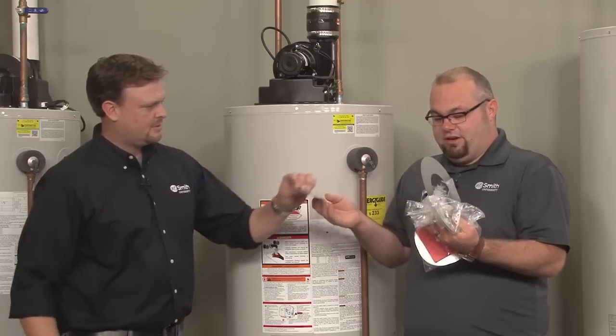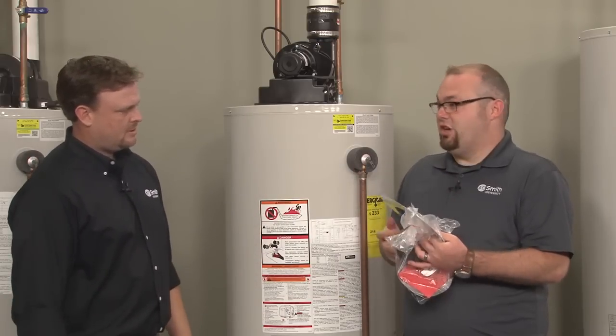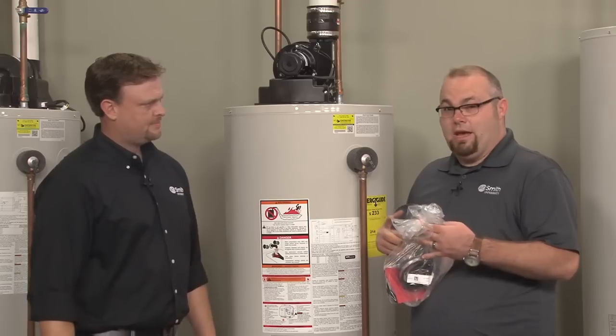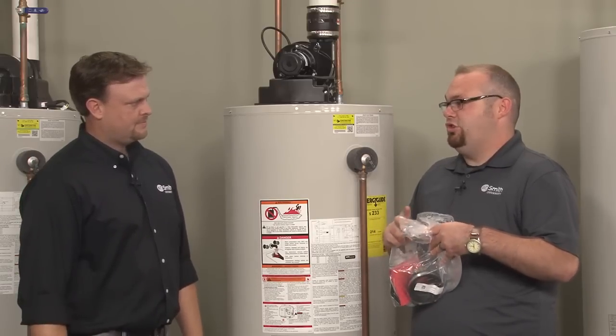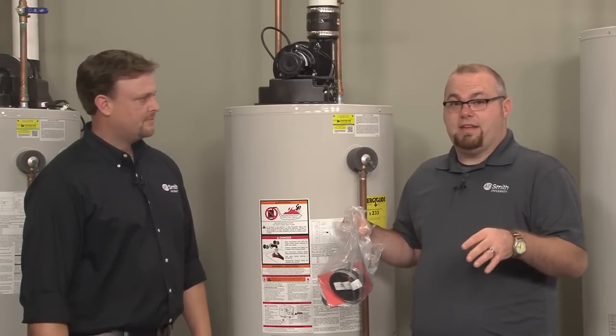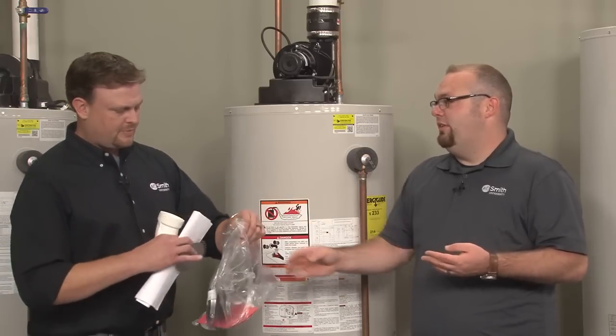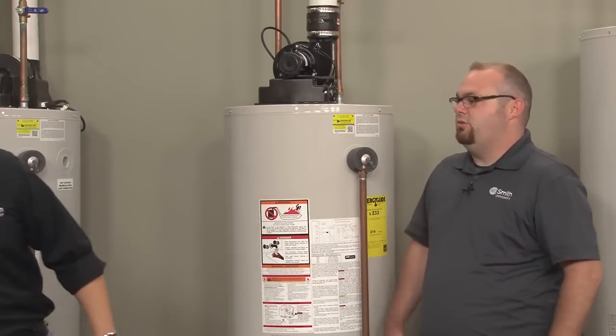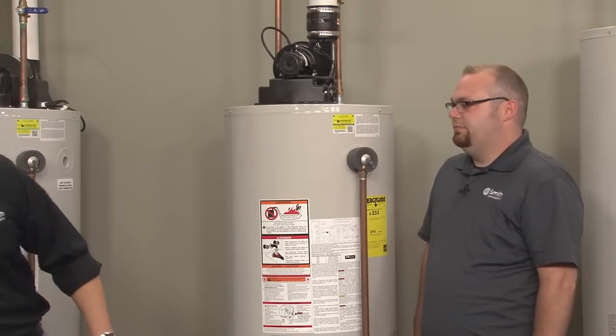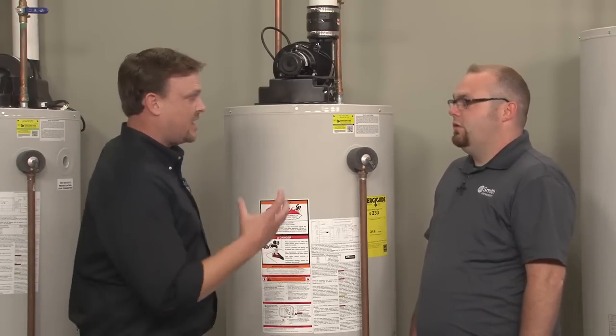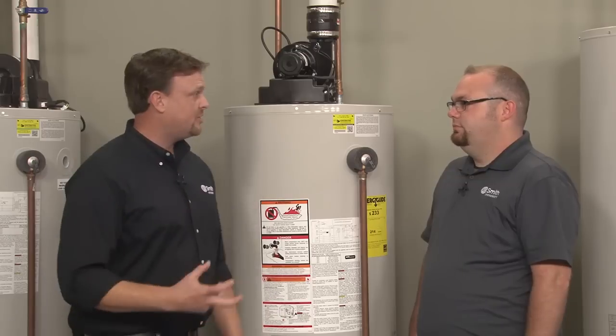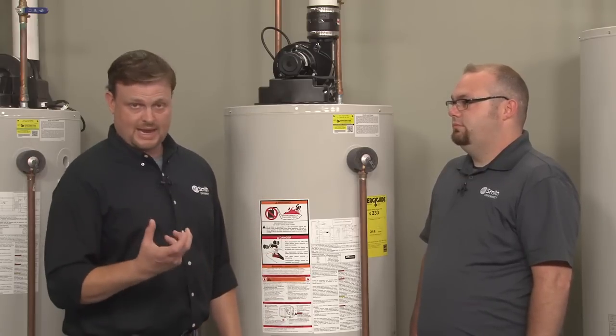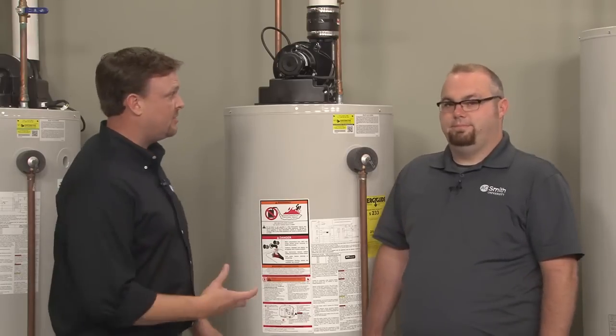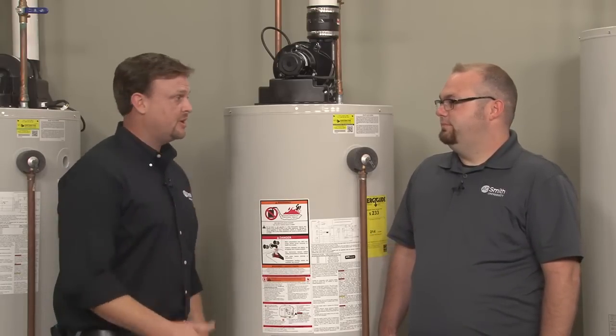Yeah. And so you have several different terminations, which is a change from the past. Always refer to the manual to make sure you're using the right termination and following the vent tables in the manual, because you don't want to vent the heater outside the parameters of what the manual states. Those termination guidelines are in the manual. They have diagrams that show you what the termination, the cap, is supposed to look like. Make sure that you're putting the right termination on the right vent length or the right size vent.